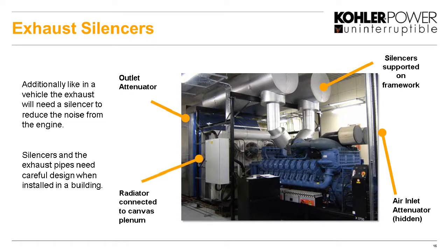So, well, one point here is just on the radiator. Obviously, we need to duct the air, and we typically have some plenum chambers around the radiator and the outlets of the building, or the container, to make sure all the air is flowing in the right location and direction to make sure we keep this completely cool.